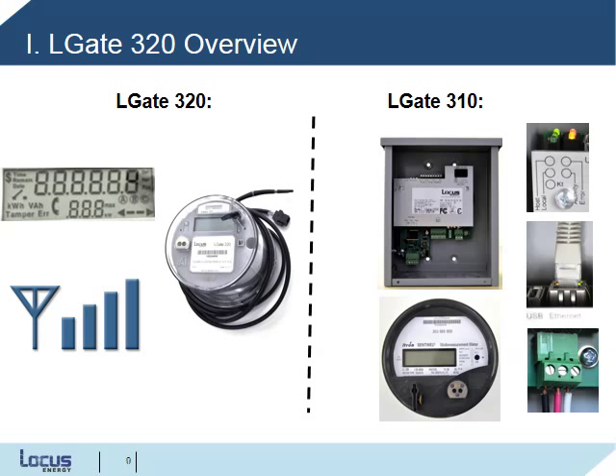In a similar vein, the LGate 320 provides for much simpler installation over a similar model, the LGate 310, which requires a separate LGate 101E data logger and Itron Sentinel power meter. The LGate 320 combines these pieces of equipment into one, so the data logger and power meter are combined. Another key difference is that the LGate 120 and 320 are far more accurate than the LGate 101 and the 310. The new meters are rated to 0.2% accuracy versus 0.5%.